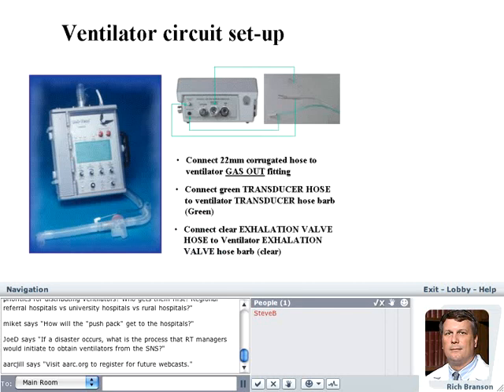And just to give you an idea, these pictures are a little small, the outlets on the top of the 754 include the circuit connections, which you see, and they're color-coded to make it easier. The green goes to the green, and the white goes to the white. The patient outlet is also where the anti-asphyxia valve is, in case you lose total gas source supply or electricity. But on either side, you see the high pressure and low pressure air oxygen, or high pressure air and high pressure oxygen inlets.